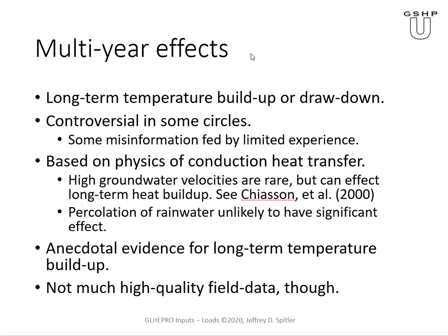There's also the possibility for percolation of rainwater. My own analysis and others is that this is unlikely to have a significant effect. Now, the water in the ground definitely has an effect. So if you go from being dry to being saturated, well, that will have a big effect on the heat transfer. But just typical rainfall percolating down through the soil, that doesn't transport a lot of energy.